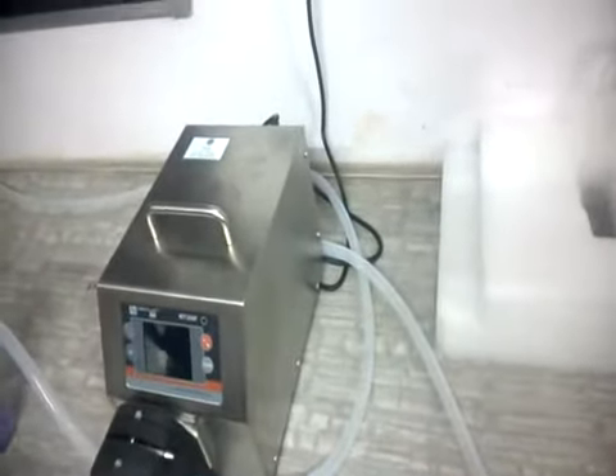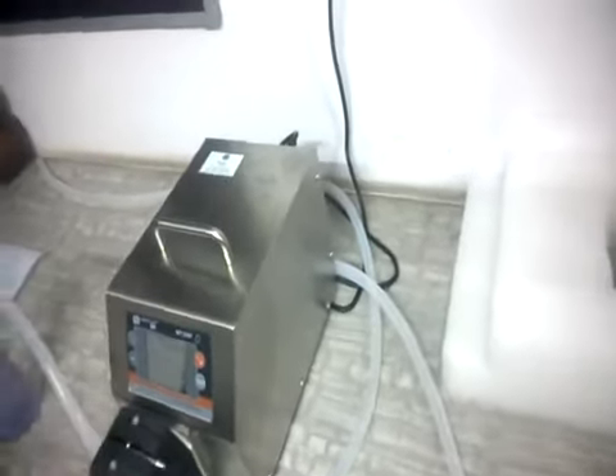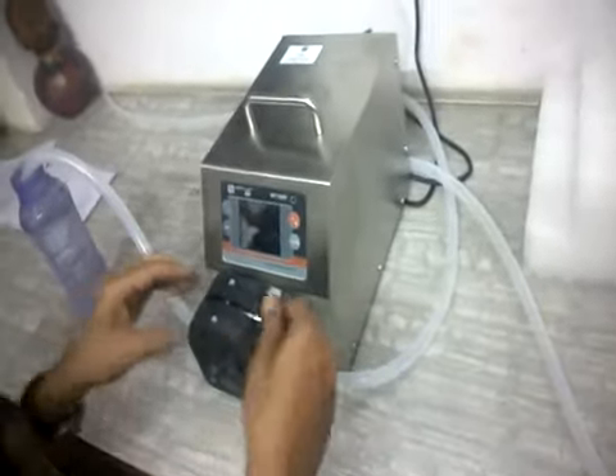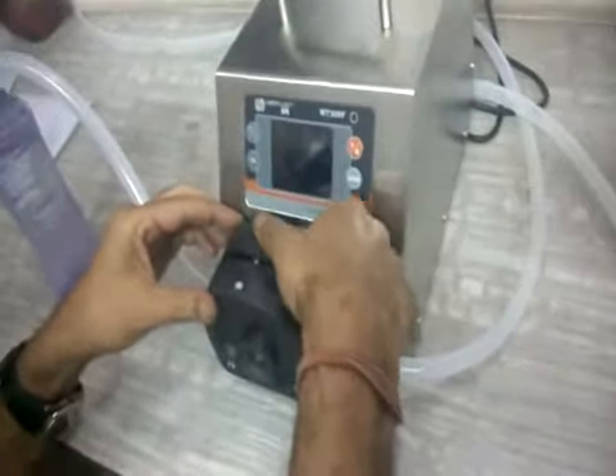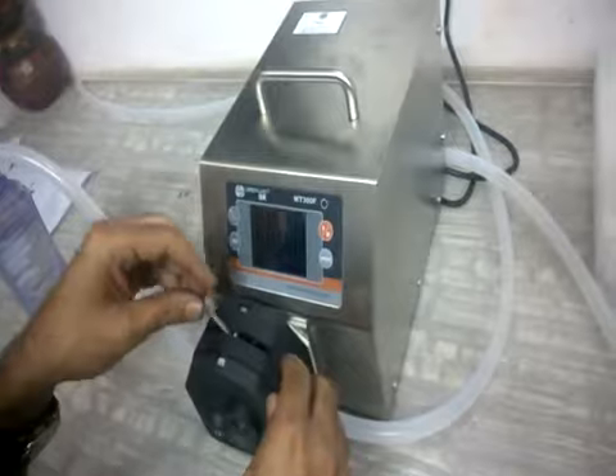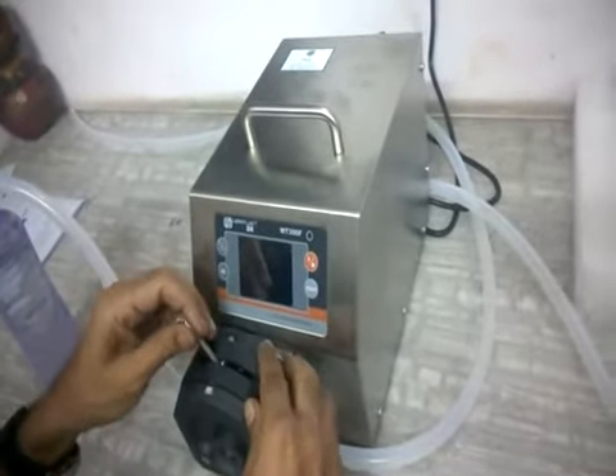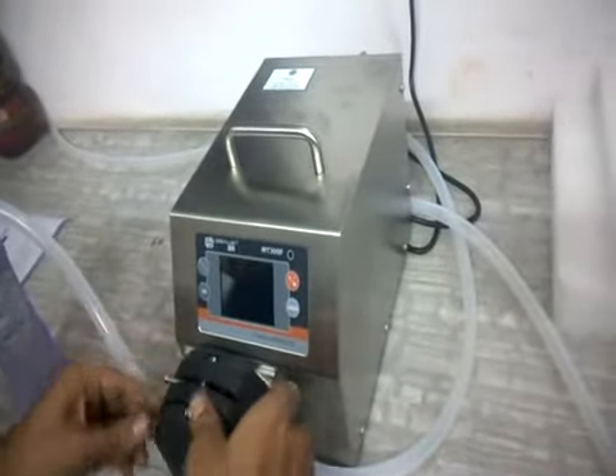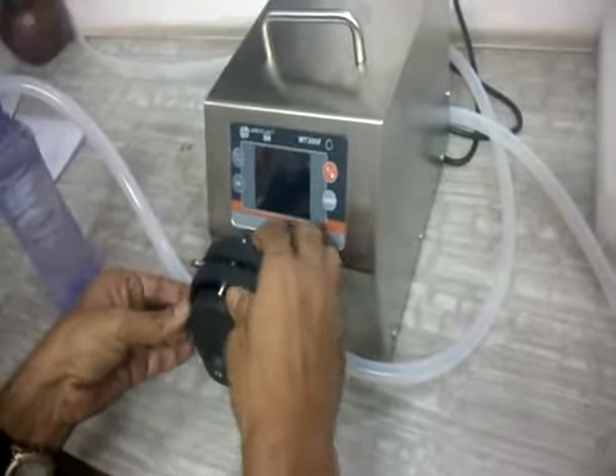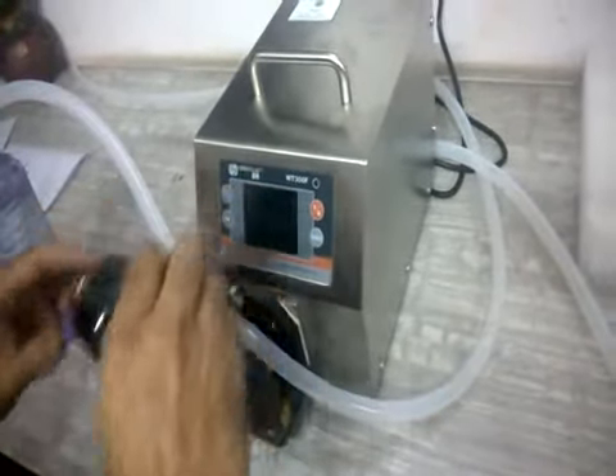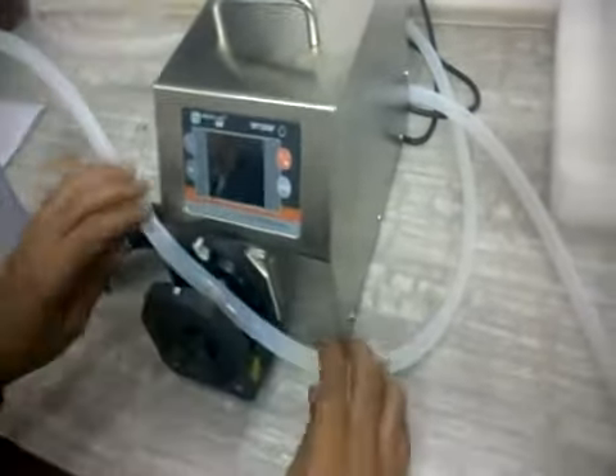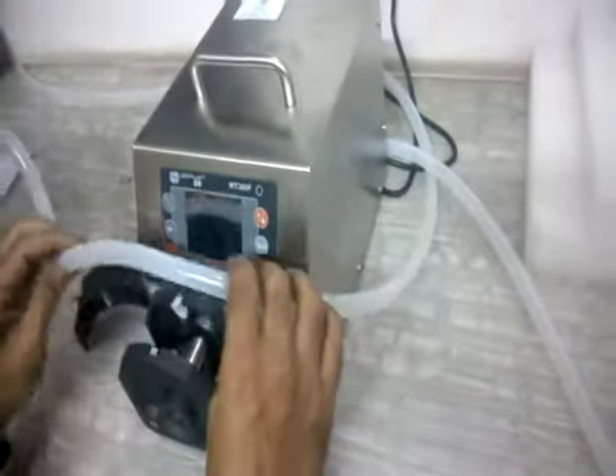So the first thing we will do is tell you how to load the tubing on the pump head. You just have to open this and it becomes loose, and you have to take out the top part. Here you can see the tubing and these are the rollers. This is a 4-roller head.